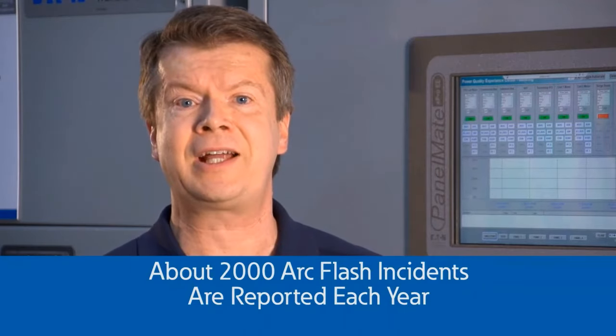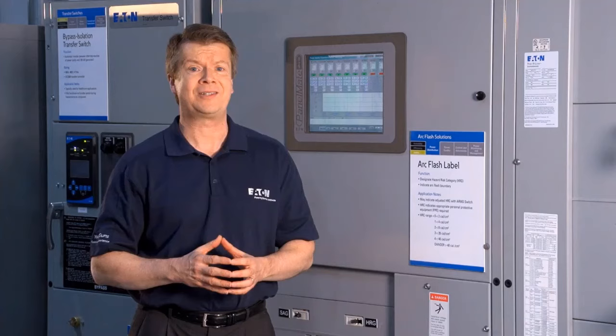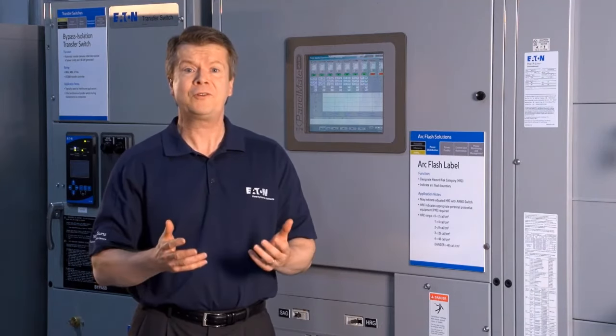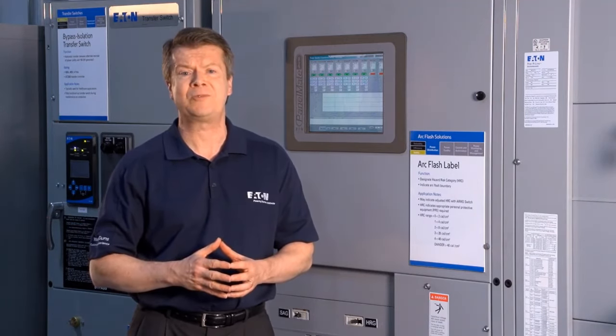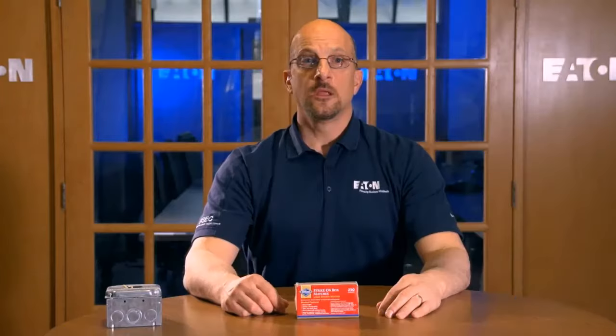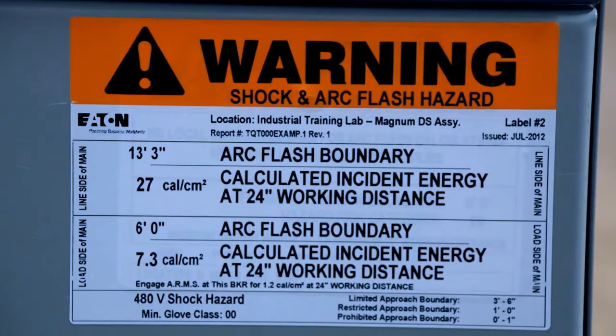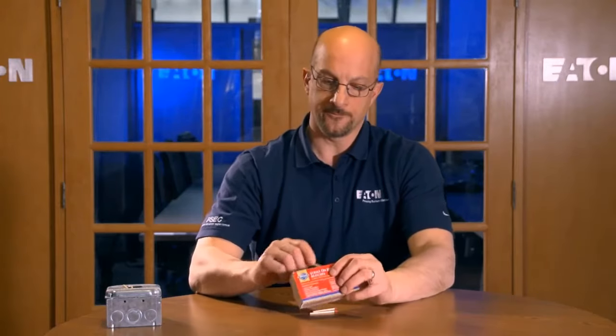About 2,000 arc flash incidents are reported each year, and as you can imagine, it is likely the actual number is significantly higher as workers are embarrassed or fearful of losing their jobs if they report a near-miss incident involving an arc flash. Arc flash energy is measured in calories per centimeter squared. An arc flash label has 2 critical pieces of information on it: the calories per centimeter squared, or the energy released, and the distance that a worker would have to stand outside to avoid a non-curable burn if an arc flash were to occur.